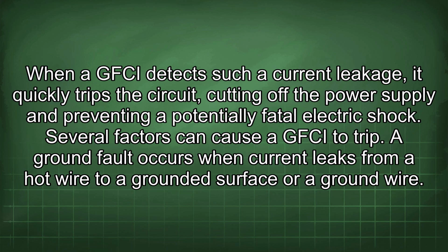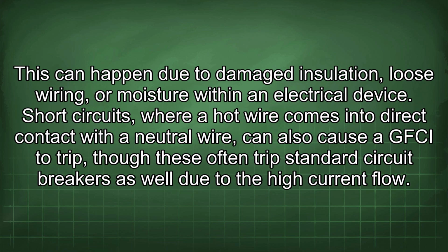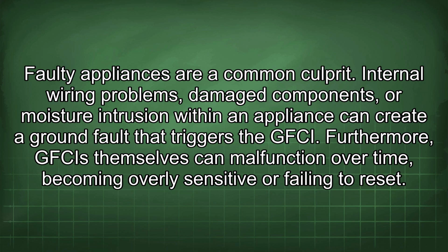Several factors can cause a GFCI to trip. A ground fault occurs when current leaks from a hot wire to a grounded surface or a ground wire. This can happen due to damaged insulation, loose wiring, or moisture within an electrical device. Short circuits, where a hot wire comes into direct contact with a neutral wire, can also cause a GFCI to trip, though these often trip standard circuit breakers as well due to the high current flow. Faulty appliances are a common culprit. Internal wiring problems, damaged components, or moisture intrusion within an appliance can create a ground fault that triggers the GFCI. Furthermore, GFCIs themselves can malfunction over time, becoming overly sensitive or failing to reset.